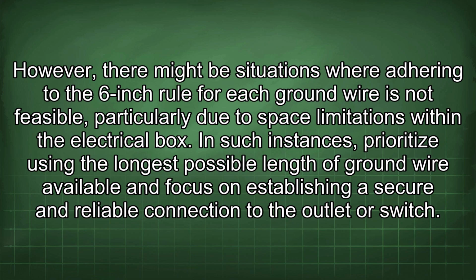However, there might be situations where adhering to the 6-inch rule for each ground wire is not feasible, particularly due to space limitations within the electrical box. In such instances, prioritize using the longest possible length of ground wire available and focus on establishing a secure and reliable connection to the outlet or switch.